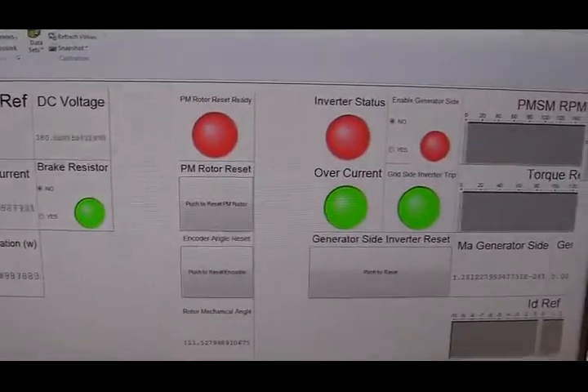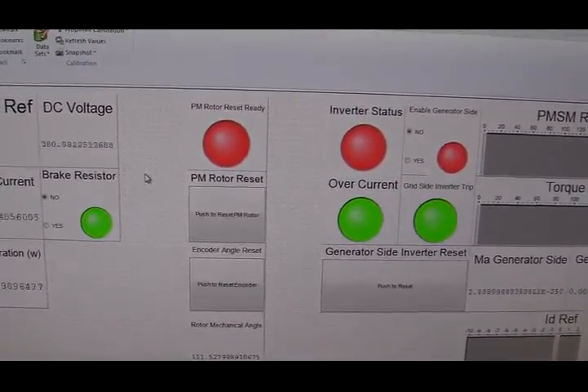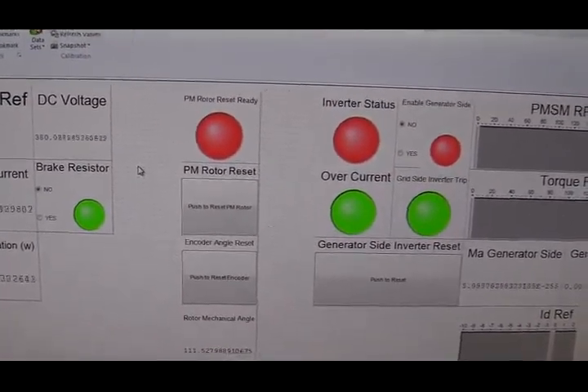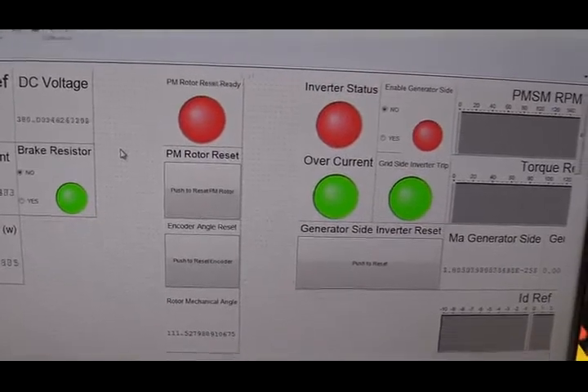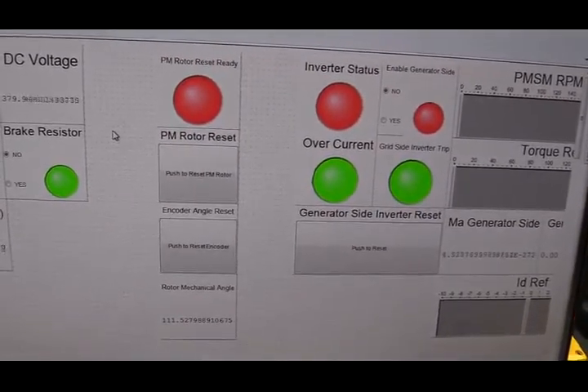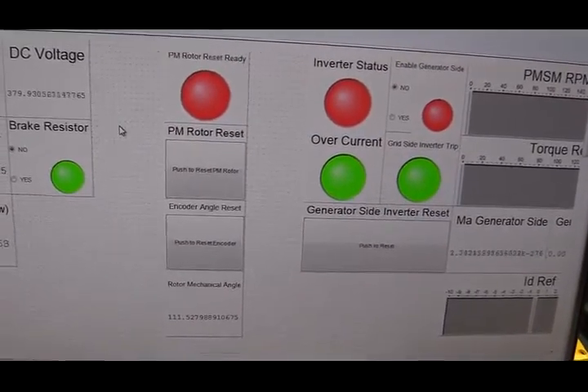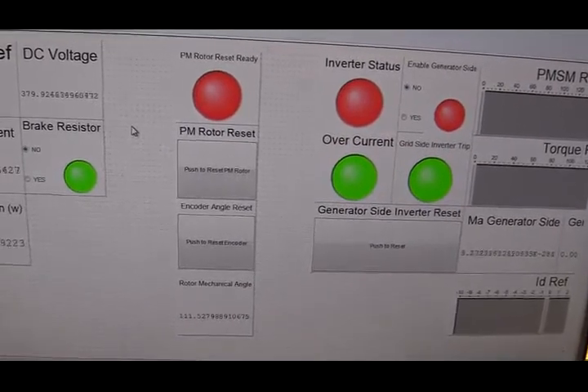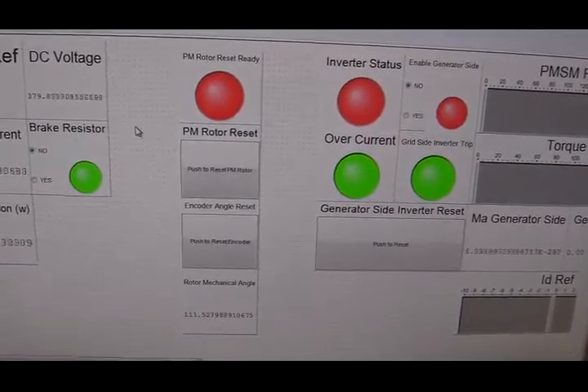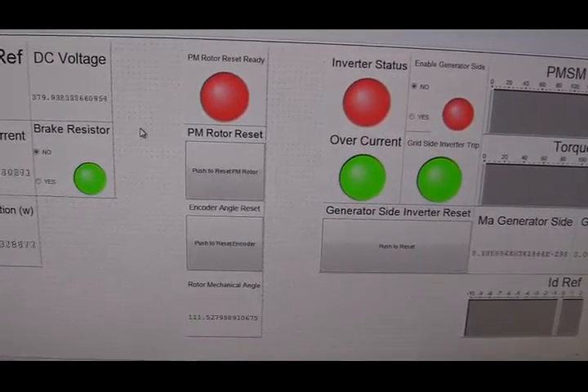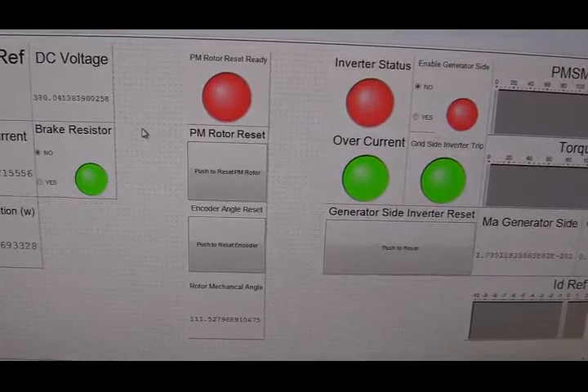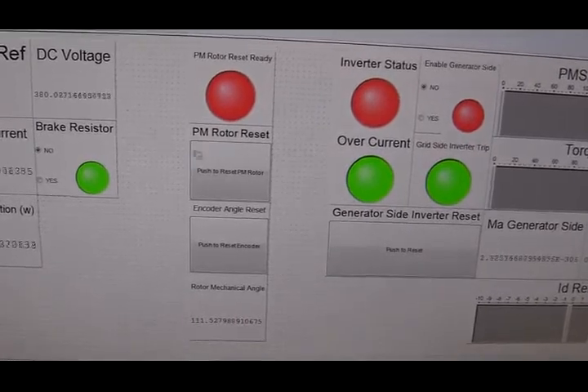Next, I'm going to give some DC current in the winding of PMSG. Why? Because we want to find the initial position. That position is defined as zero in the controller. Otherwise, we'll mess up with the control. So we first have to give some DC current in the winding of PMSG.